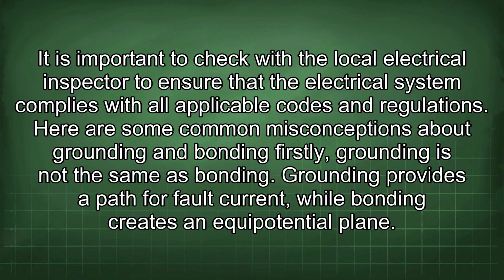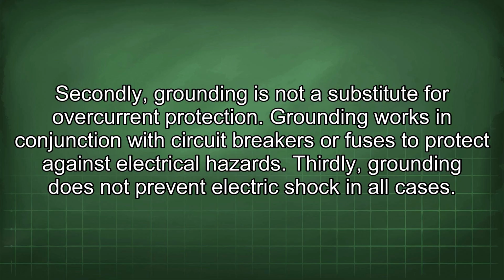Grounding provides a path for fault current, while bonding creates an equipotential plane. Secondly, grounding is not a substitute for overcurrent protection. Grounding works in conjunction with circuit breakers or fuses to protect against electrical hazards. Thirdly, grounding does not prevent electric shock in all cases.